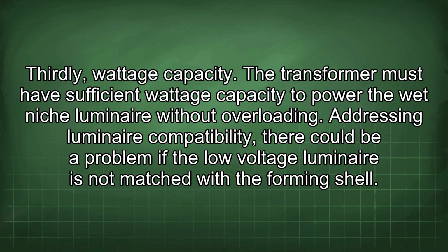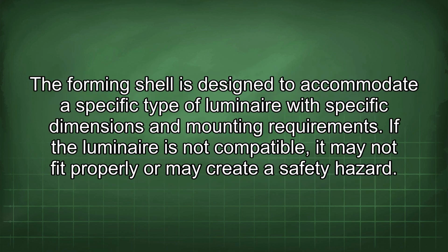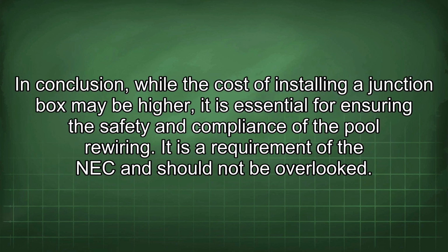Addressing luminaire compatibility, there could be a problem if the low voltage luminaire is not matched with the forming shell. The forming shell is designed to accommodate a specific type of luminaire with specific dimensions and mounting requirements. If the luminaire is not compatible, it may not fit properly or may create a safety hazard. In conclusion, while the cost of installing a junction box may be higher, it is essential for ensuring the safety and compliance of the pool rewiring. It is a requirement of the NEC and should not be overlooked.